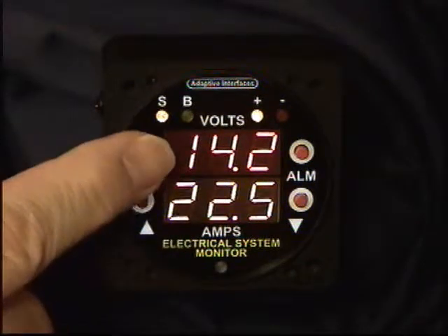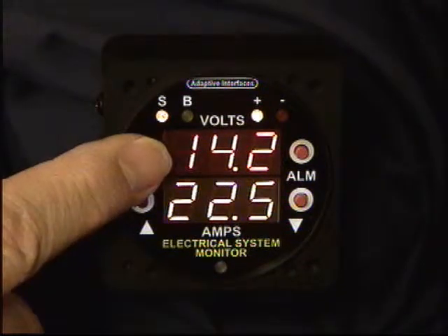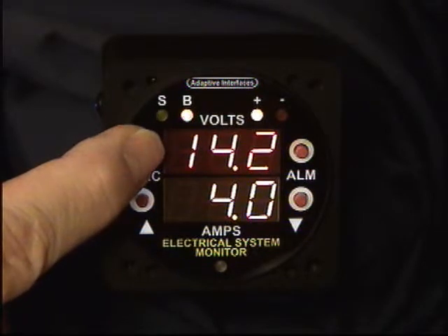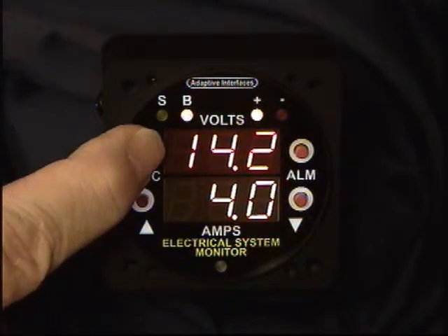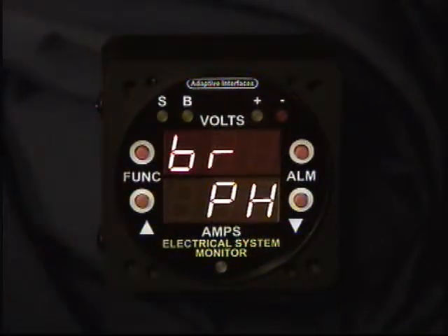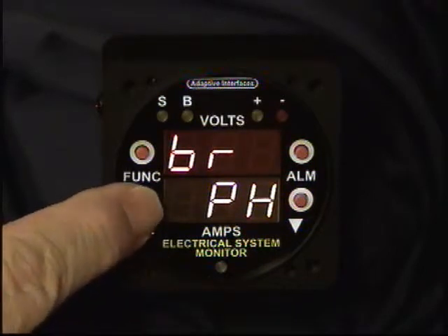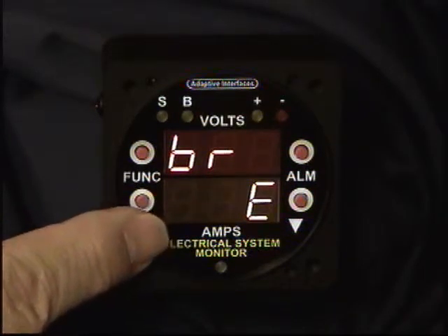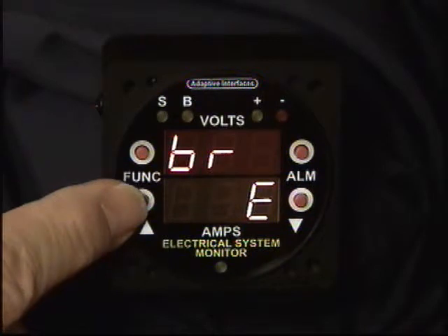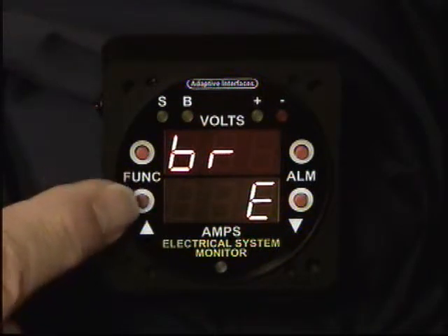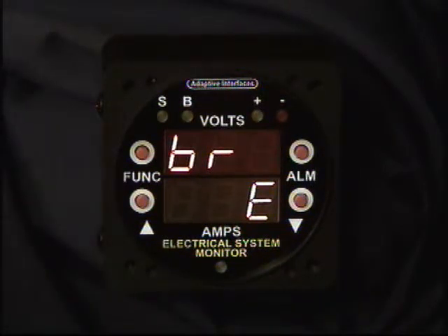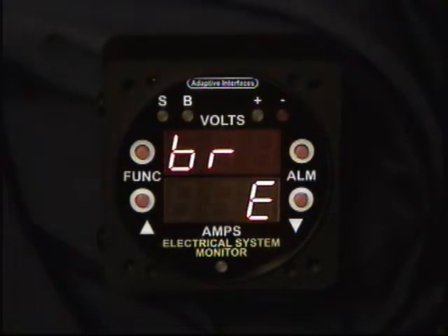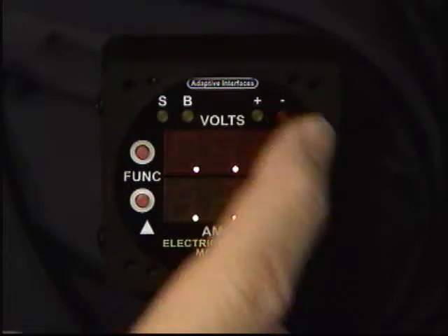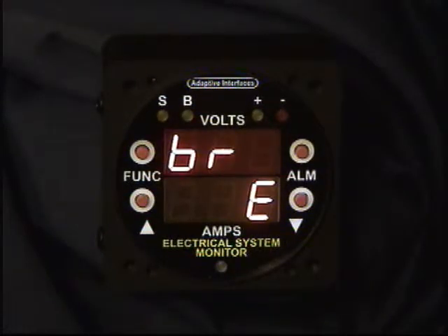Let's go through some of the other methods of controlling the brightness. We'll hold the function key in for 5 seconds, get to menu level 1, and the other option for controlling the instrument brightness is E, or external. This would be controlled by an external voltage, which could be a potentiometer or a control on the instrument panel. So let's go ahead and do that. We'll enter that.